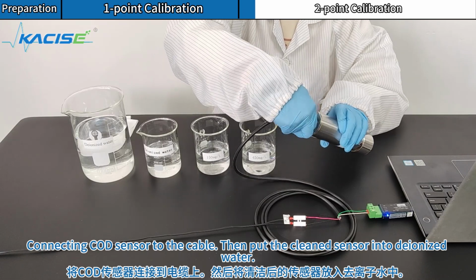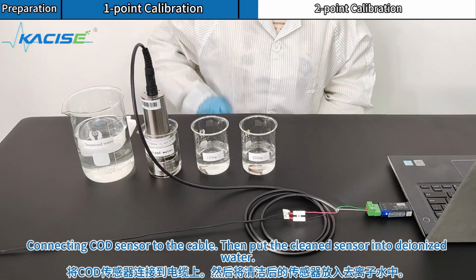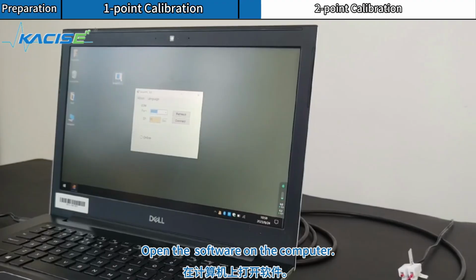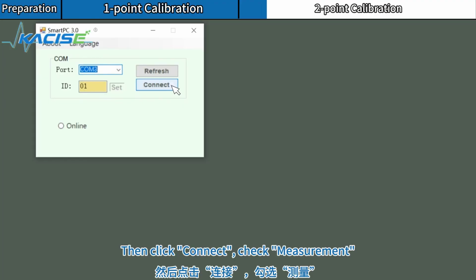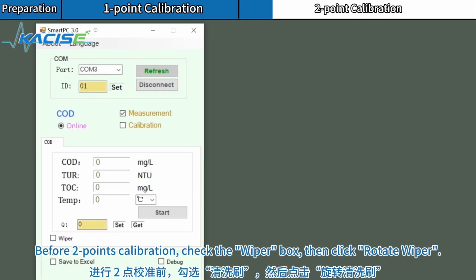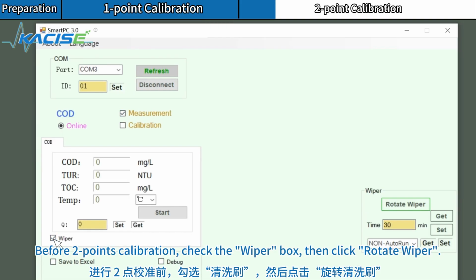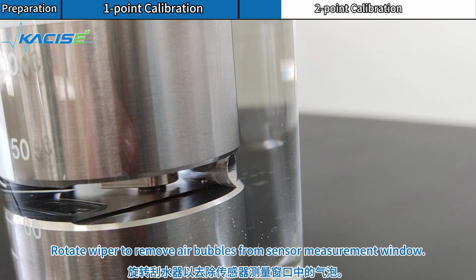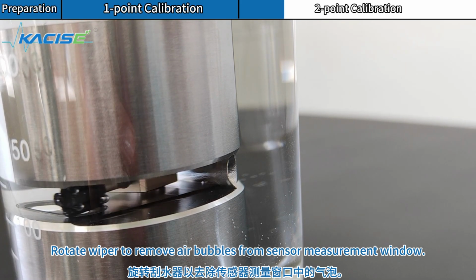Then put the cleaned sensor into deionized water. Open the software on the computer. Then click Connect. Check Measurement. Before 2 points calibration, check the wiper box, then click Rotate Wiper. Rotate wiper to remove air bubbles from sensor measurement window.